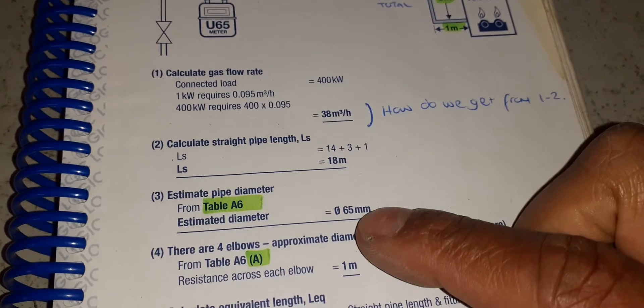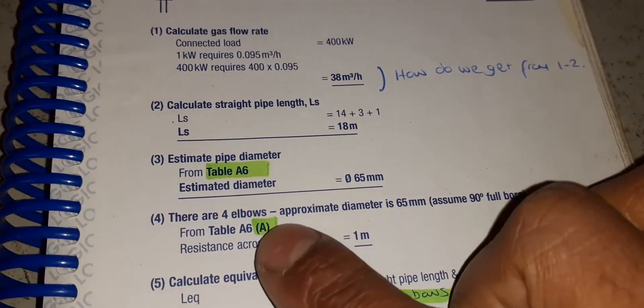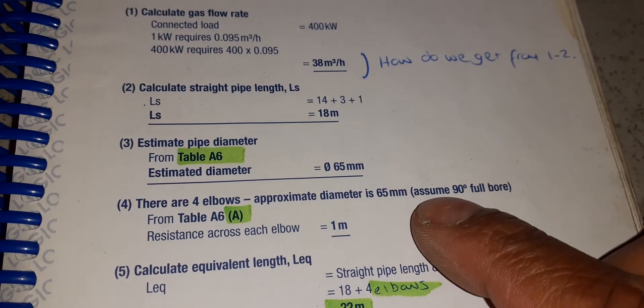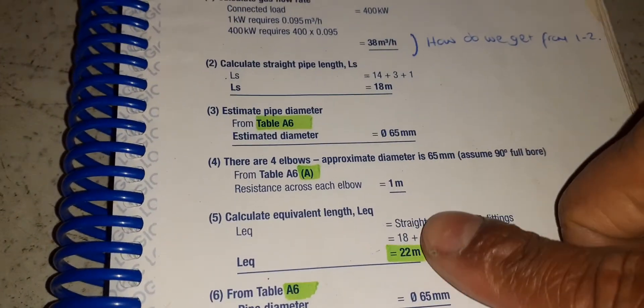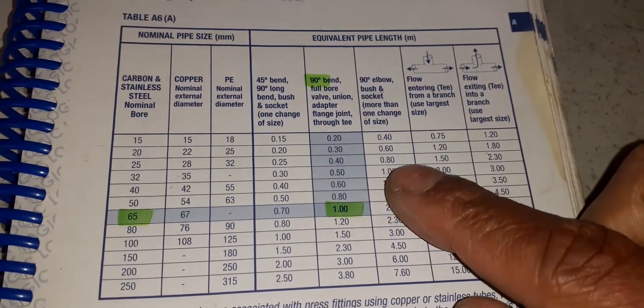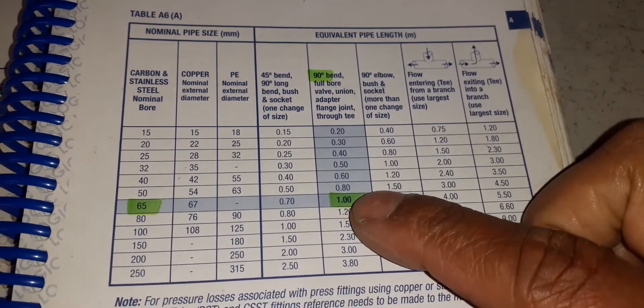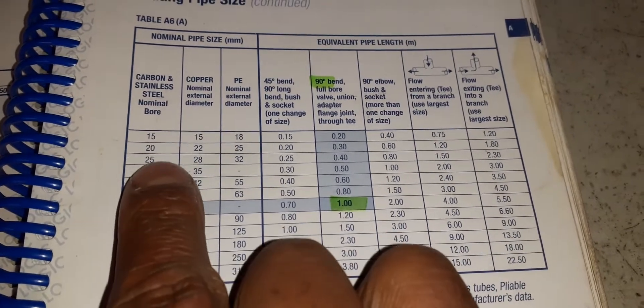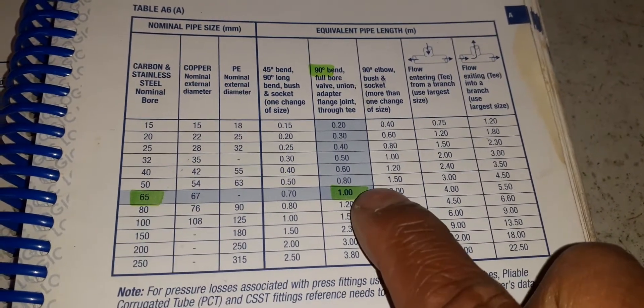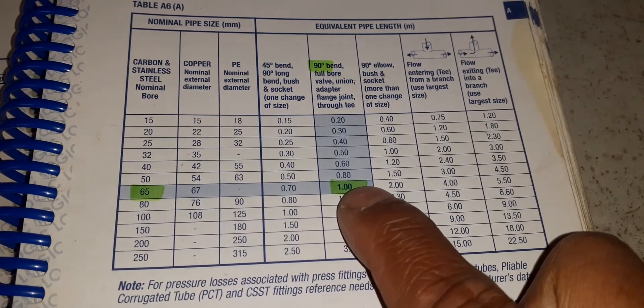So now to add restrictions - there are four elbows, approximate diameter is 65 millimeters. So in order to see restrictions for elbows or tees and so on, in our book here it shows us this is our type of pipework that we're dealing with: 65 millimeters, one meter worth of restriction for every elbow.